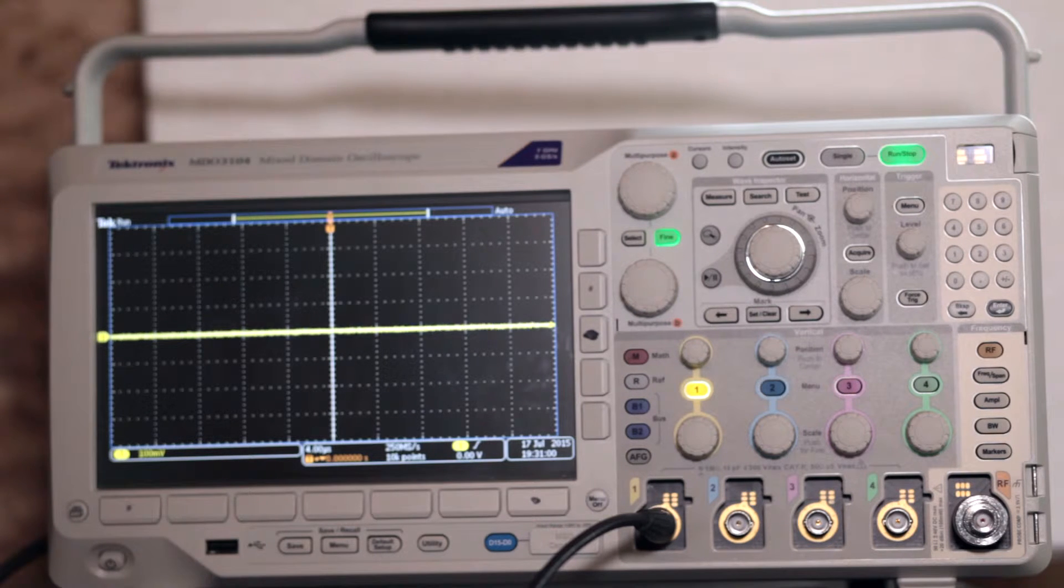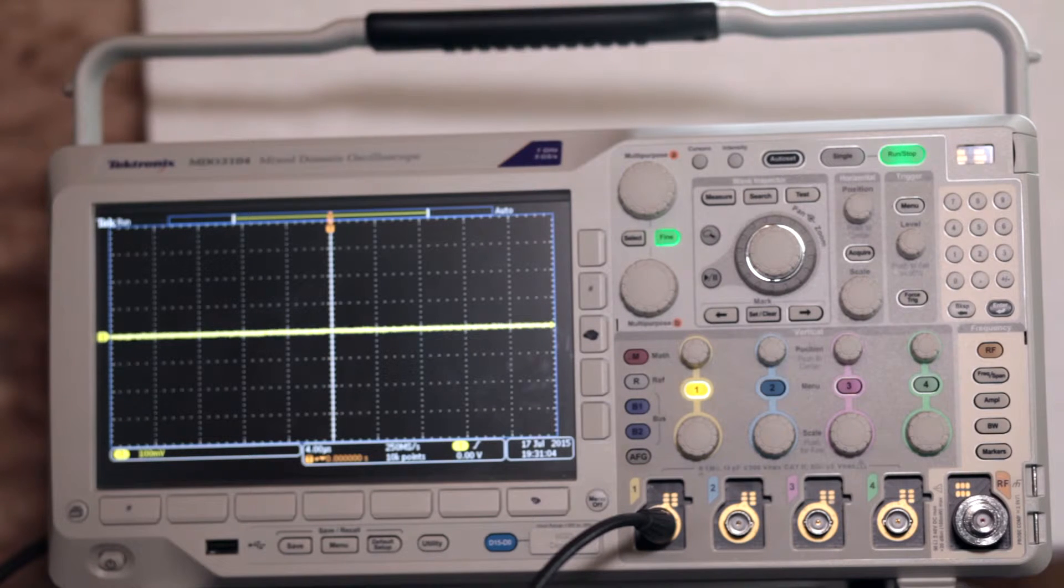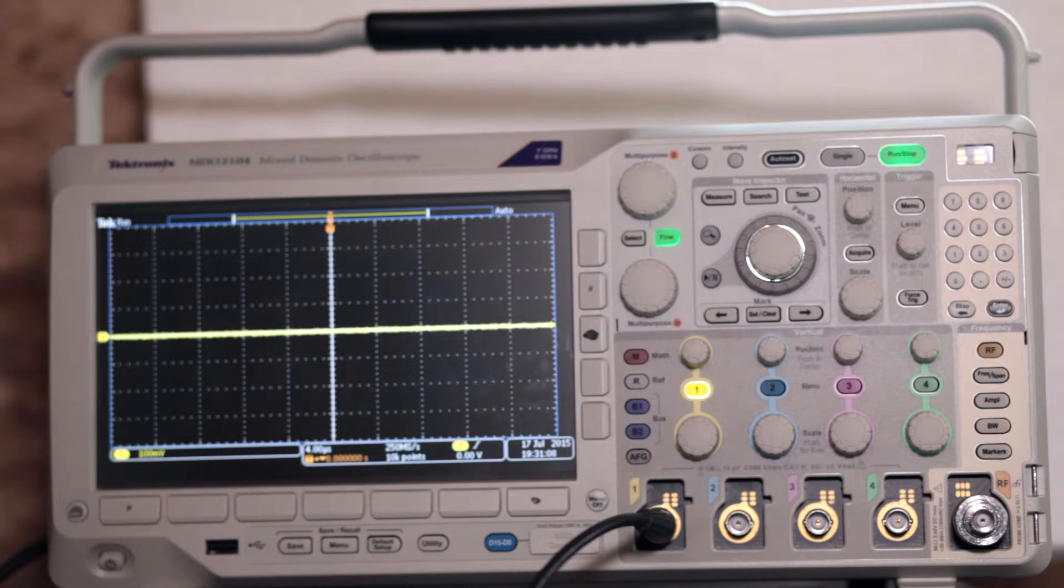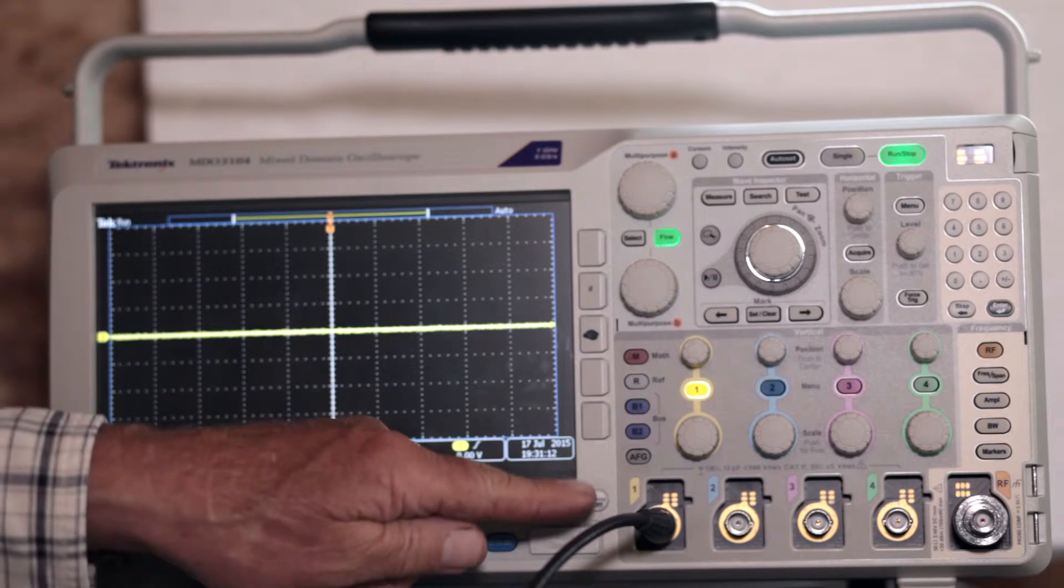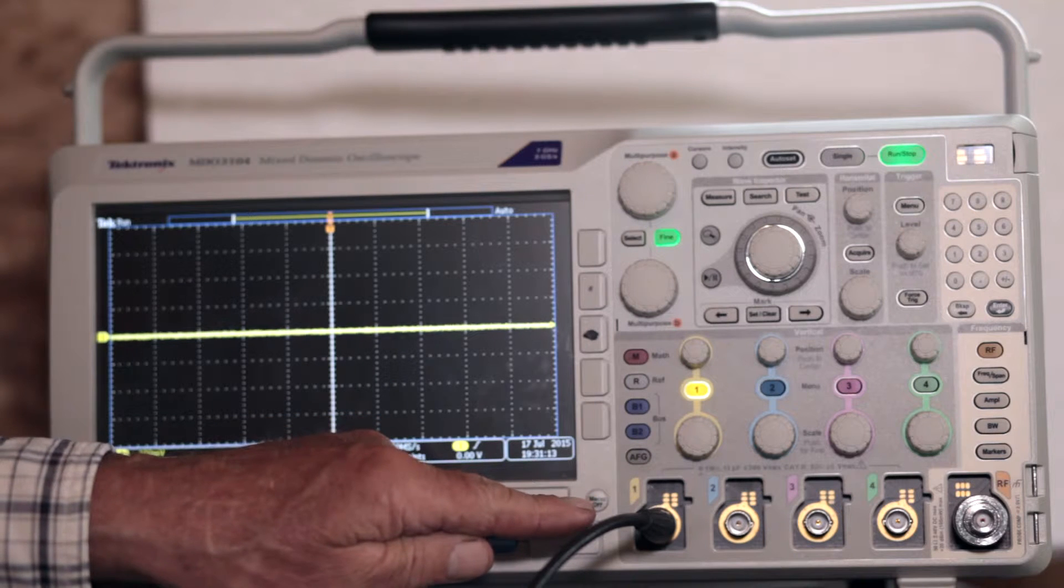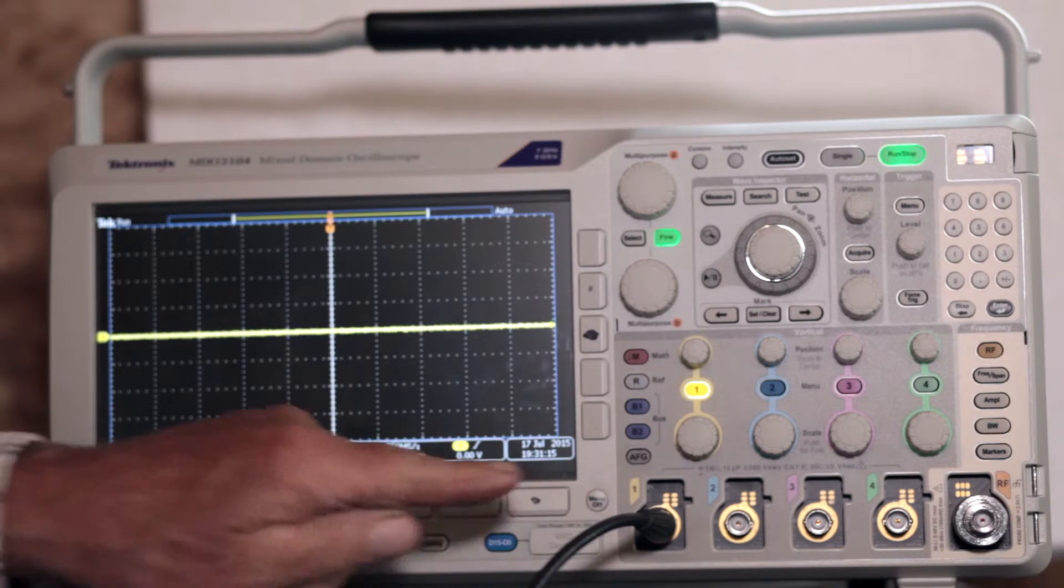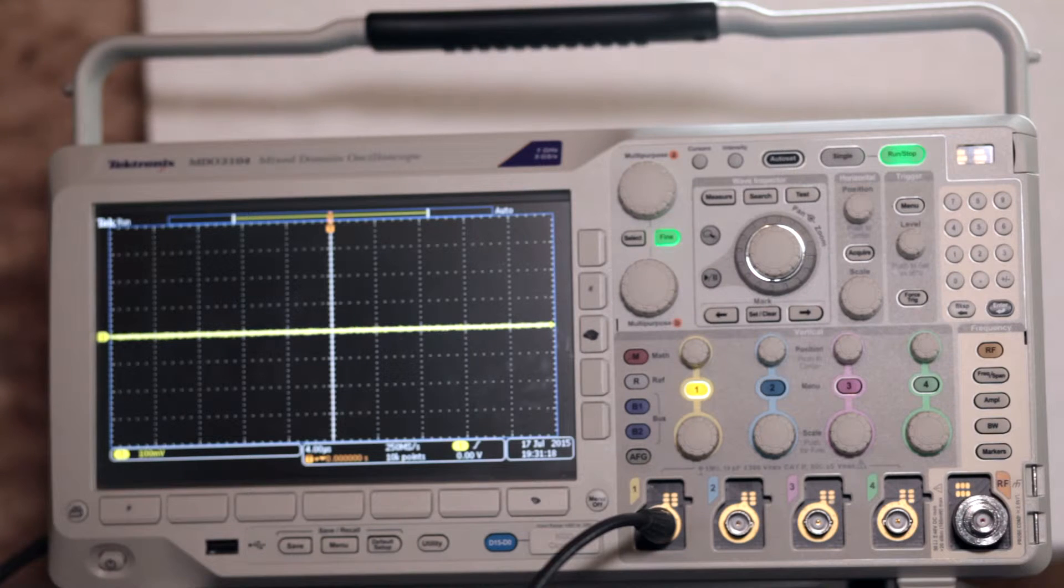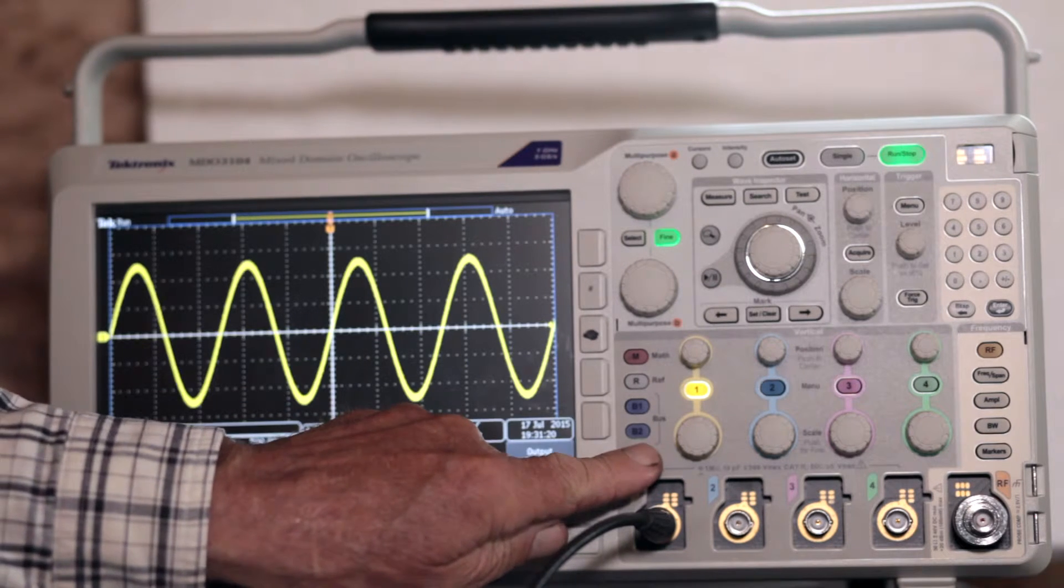To see how this works in the real world, we've connected a BNC cable to the AFG output on the oscilloscope rear panel and hooked the other end of the cable to an analog channel input at the front. Then, after the instrument has booted up, press AFG, the bottom button, in the vertical column to the left of the channel 1 controls.